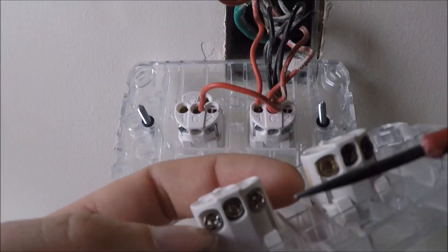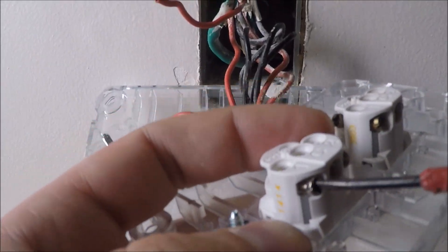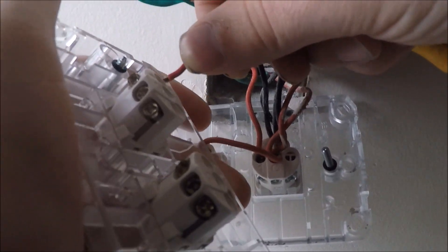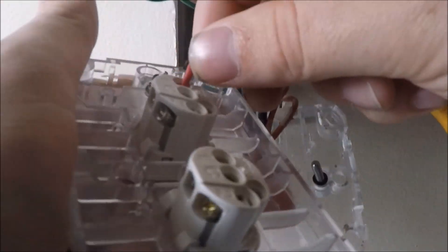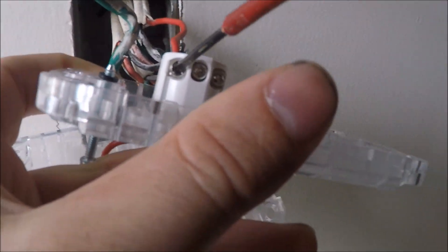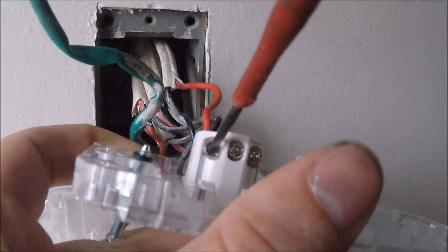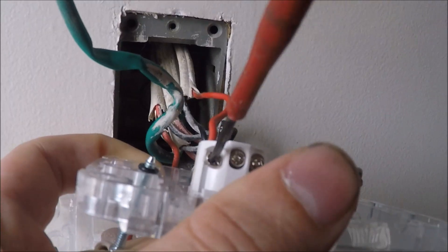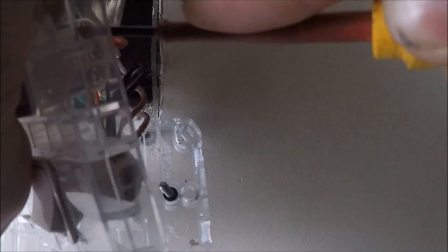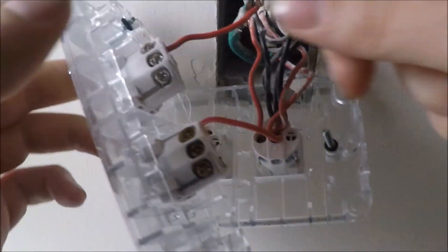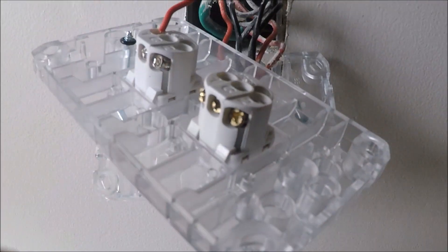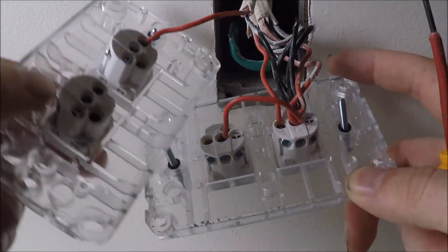Okay that's pretty good. Now you get your switch number one on top, check it in there. Make sure the screw terminal is going to tighten up on the copper of the cable by looking down where your cable was sitting. Screw it in. And then give it the pull test. Perfect, it's not going to come out, it's nice and tight there.